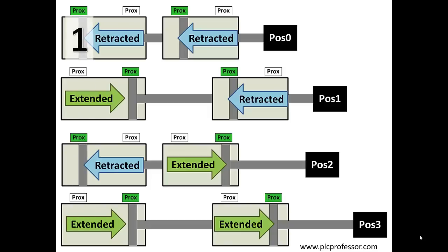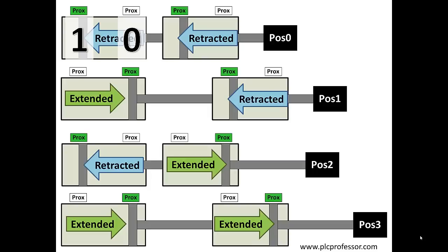When the code executes, it examines the bit in memory associated with the input location that the field wiring of each switch points towards. If the switch is on, it reads a 1. If the switch is off, it reads a 0. So just in looking at that one cylinder, you have two bits, and two bits give you four possible combinations. So if you were to convert that from binary to decimal, remember the first position, the least significant bit is to the right, most significant to the left when looking at binary values in memory. So the first position, the least significant, is units, and the next one is 2. So you have 1, 2, and no units. So the decimal equivalent of 1, 0 is 2. And there are four possible combinations: 0, 0, 0, 1, 1, 0, and 1, 1. Or 0, 1, 2, and 3 in decimal.